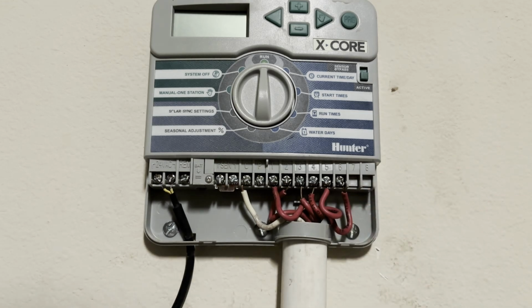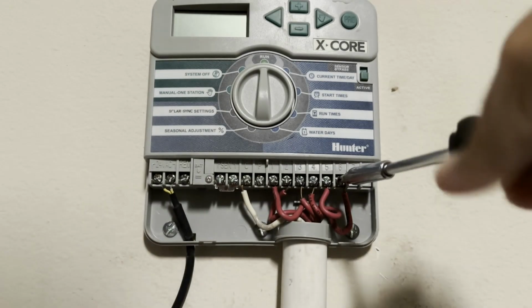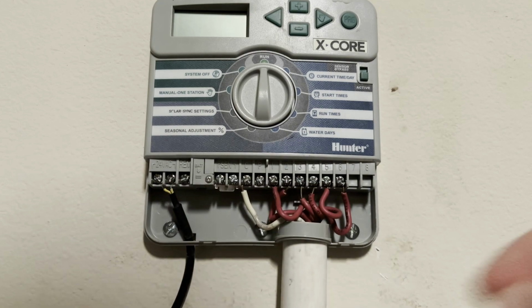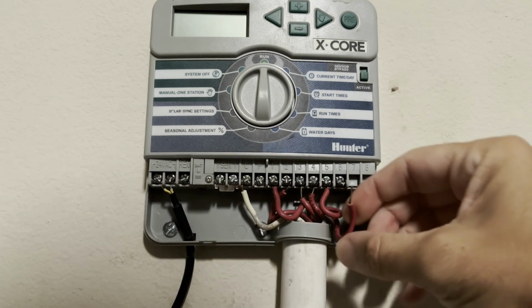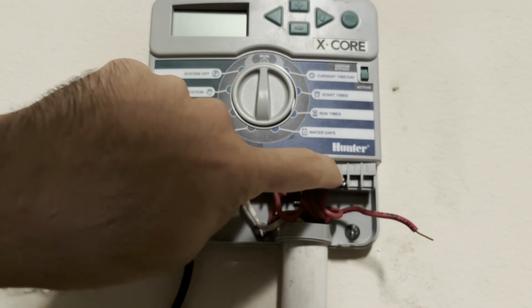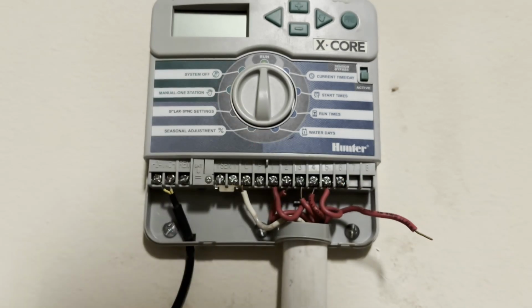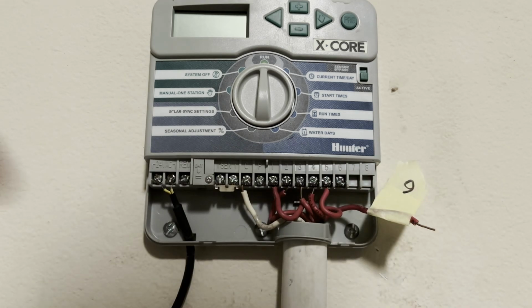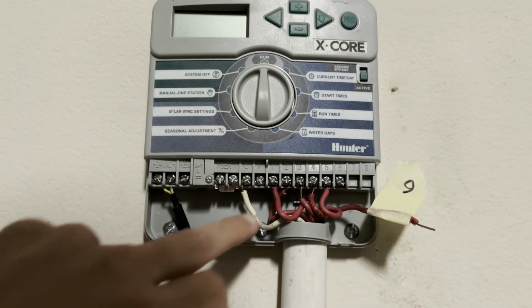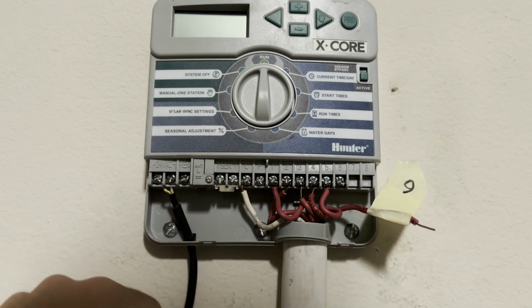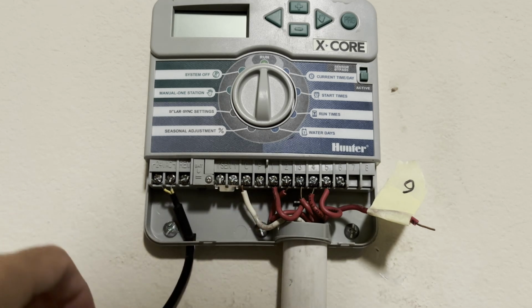These are just Phillips head screws that we'll unscrew one at a time. Once loose, you can pull the wire straight out. I'll label this one zone 6, since it's connected to the number 6 terminal, and repeat this for the other five zones and the white wire. You don't have to worry about the transformer wire, since your new unit will come with a new transformer.